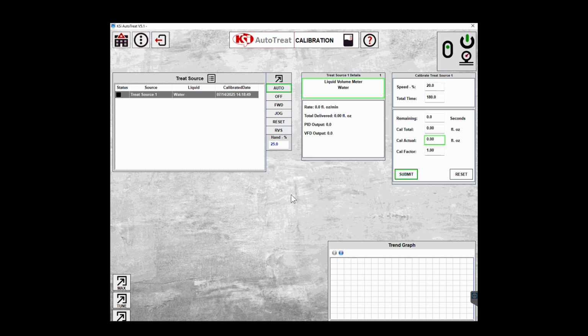To begin calibration, ensure that both valve handles on the pump stand are set to calibrate, in cal. Select the desired treat source from the grid on the left, which will populate the associated fields on the right. Click and hold the jog button to pump liquid into the calibration tube until it reaches the 0 ounce mark. If the liquid level is above 0, drain the tube back until it aligns with 0.